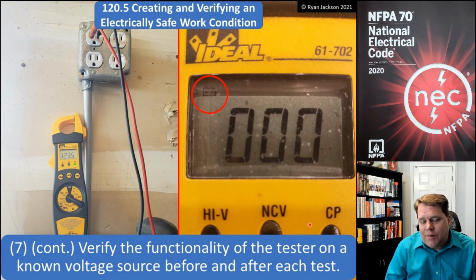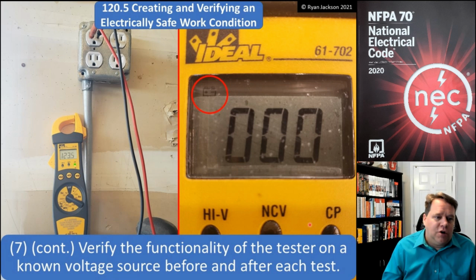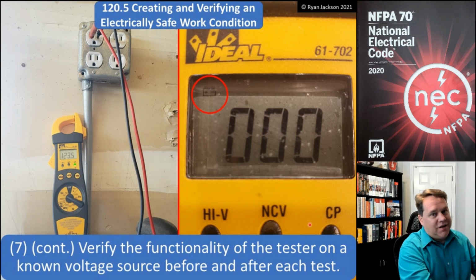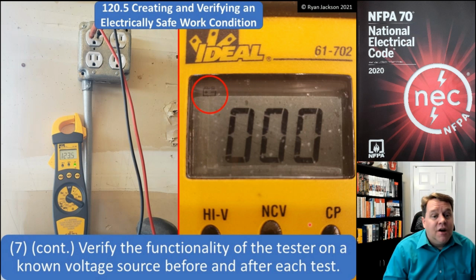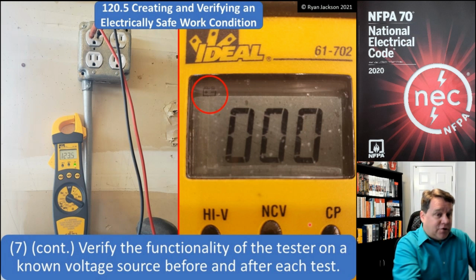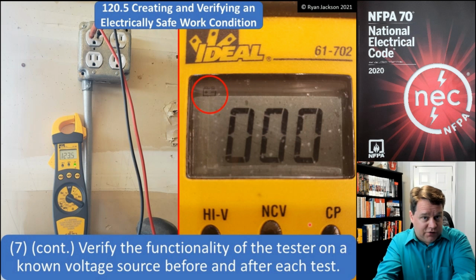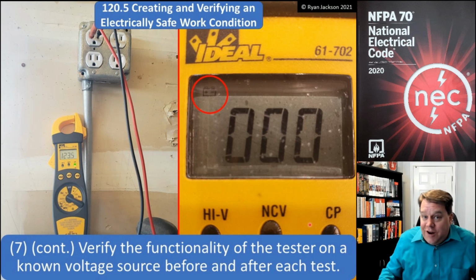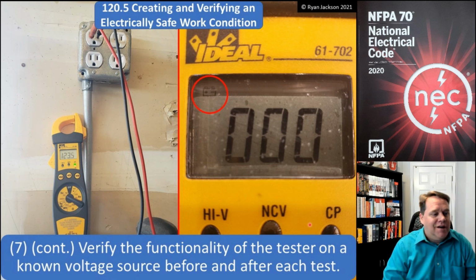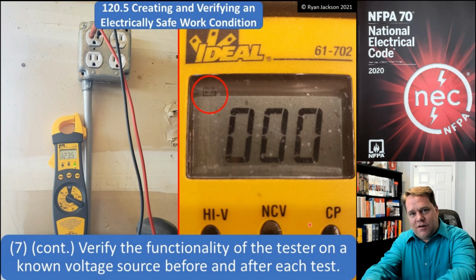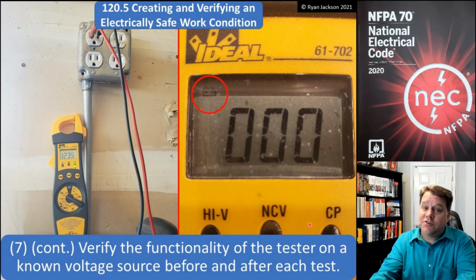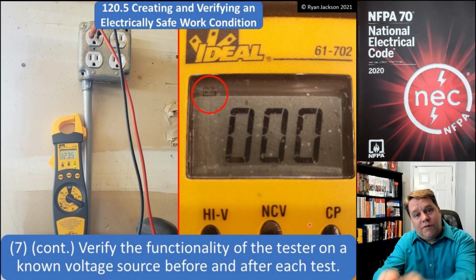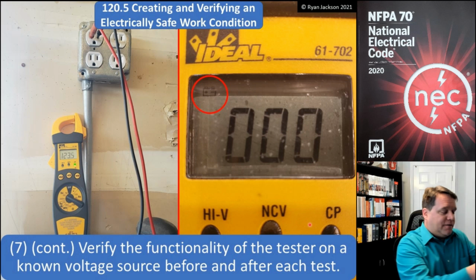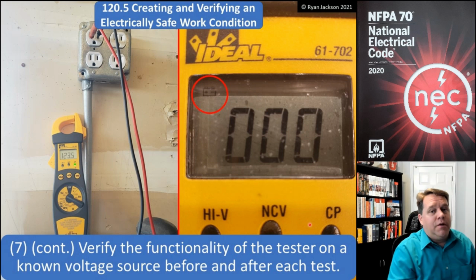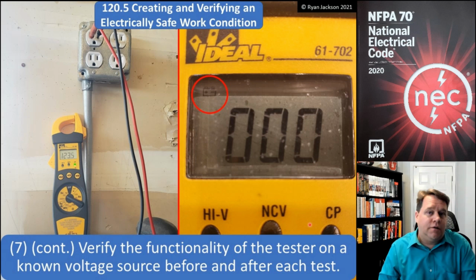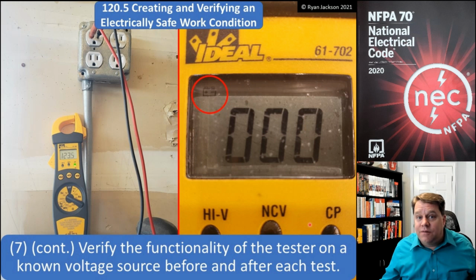So strange things happen. This seems like so much work, and it's like, oh, check the tester, check the thing, then check it again. Seriously? Well, weird things happen. Could this meter have died after I checked the meter and before I checked the circuit? Sure, that battery was ready to die. It could have happened. Can you imagine? You test it, this is good, and then you test the circuit and it says it's off. Not because it's off, but because your battery died. So once we verify that there is no voltage, let's verify that your meter actually works. We're going to check that your meter works before and after you verify the absence of voltage. Look, stranger things have happened.